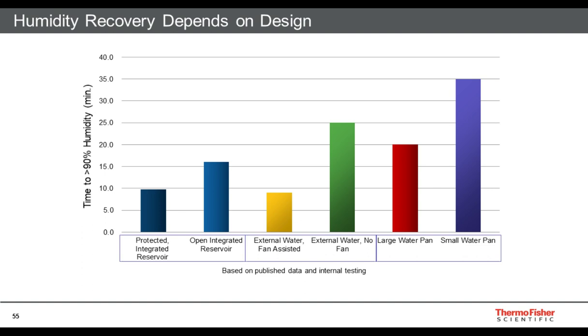So again, left to right, the dark blue bar shows humidity provided by a protected or covered integrated water reservoir. So this is built into the floor of the incubator. And the recovery there is less than 10 minutes. That's very fast. Humidity is very difficult to recover fast. Next to that, the bar to the right, the other blue bar, is a similar built-in integrated water reservoir without a cover. And you can see that removing the cover slows recovery a little bit, and this makes sense because as you keep things covered, they're going to dry out less, so you get higher humidity.